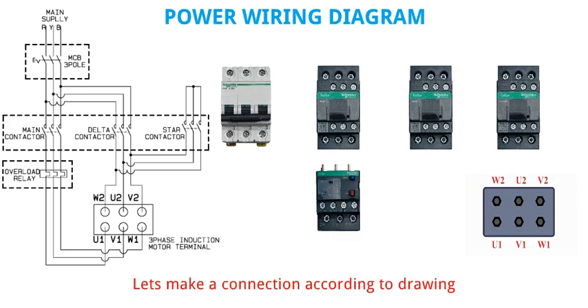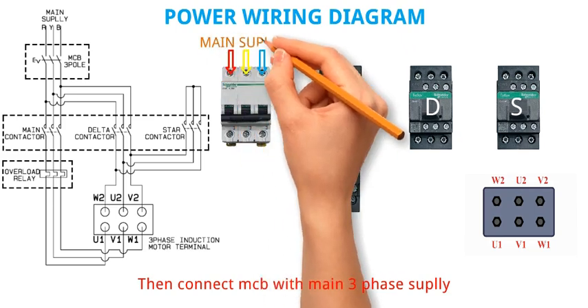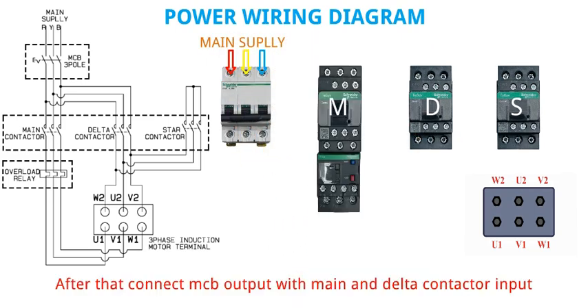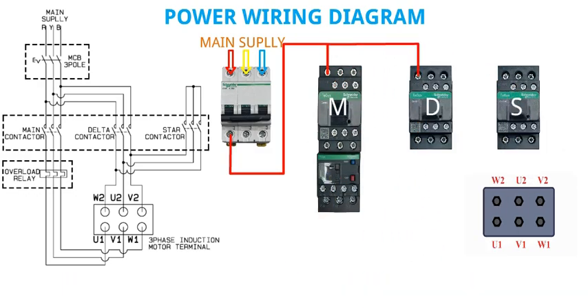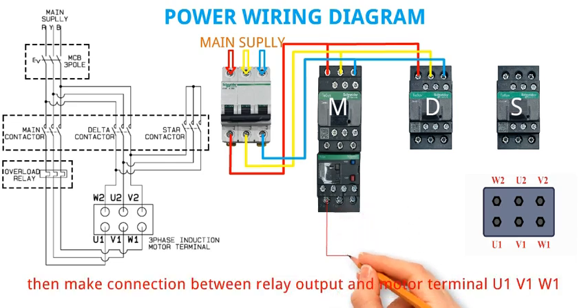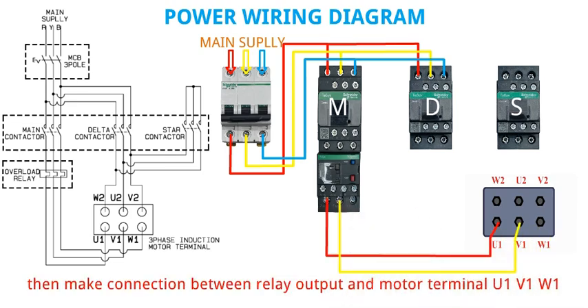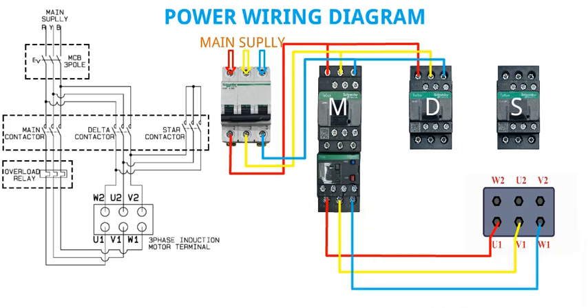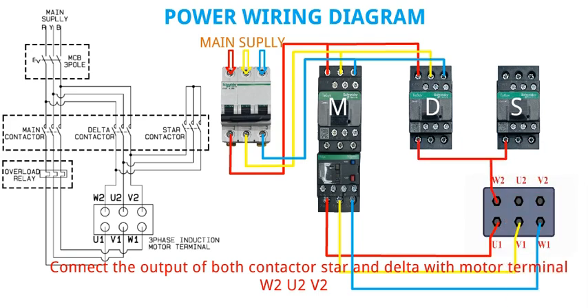Let's make a connection according to the drawing. First connect main contactor with overload relay. Then connect MCB with main 3-phase supply. After that connect MCB output with main and delta contactor input. Remember that phase sequence should not change during power wiring of star delta starter. Then make connection between relay output and motor terminal U1 V1 W1.